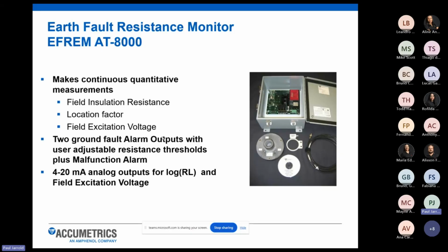So our system is designed to give you a warning alarm to let you know you're dropping to a low value, however, not at a ground fault state yet. But then once you continue to drop in value, more current is lost, you will trigger the ground fault alarm.